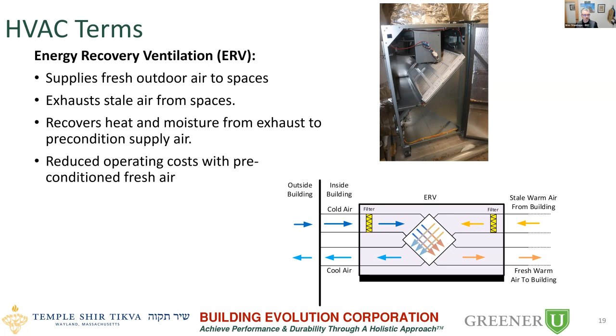And in the summertime, for those who are in Massachusetts, you'll know it's usually hot and muggy outside. So it takes a lot of energy to cool it down and dehumidify the air. If you're already conditioning the space indoors and you're exhausting that air, you're wasting that energy. So the energy recovery ventilation recaptures that energy by preconditioning the outdoor air, but it's not cross-contaminating the air streams between them. So you're still getting fresh air into the space, but it's already preconditioned most of the way to the temperature and humidity you want for indoor conditions.